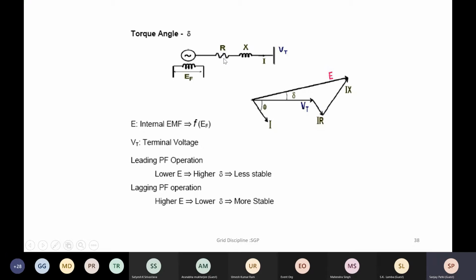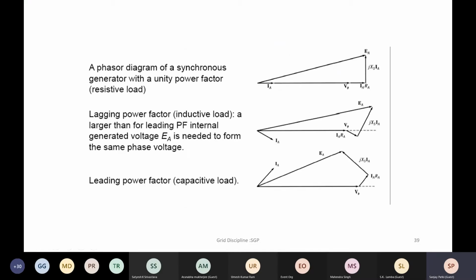And this reactance and this resistance governs this angle between Vt and E, and this becomes your load angle. So the idea of explaining this to you is that this is your key parameter as far as the generator operation is concerned, and the generator's ability to deliver MW as well as reactive power is basically governed by this equation and the angle between E and Vt. This is your load angle of the generator. This is basically the purpose of this slide.